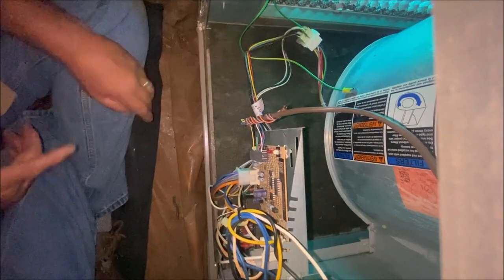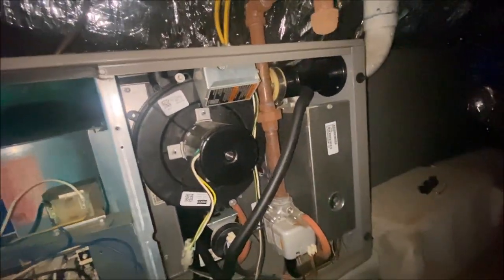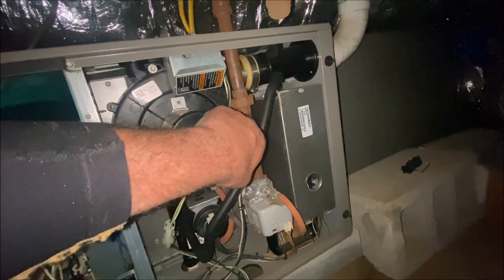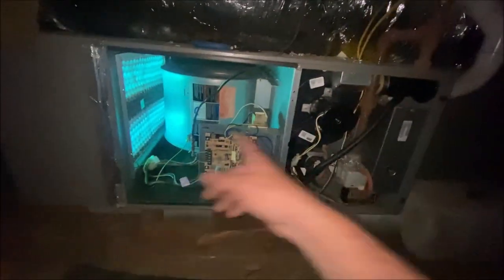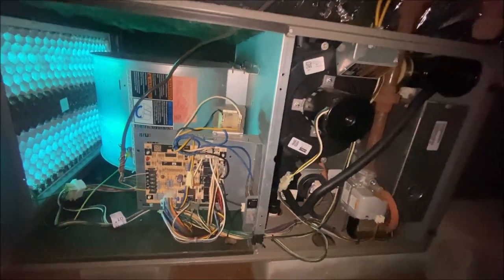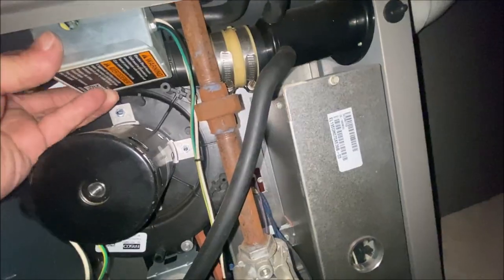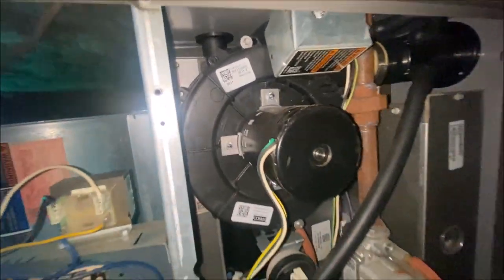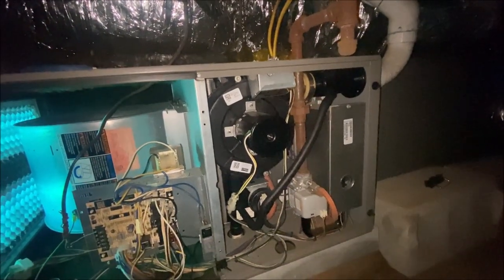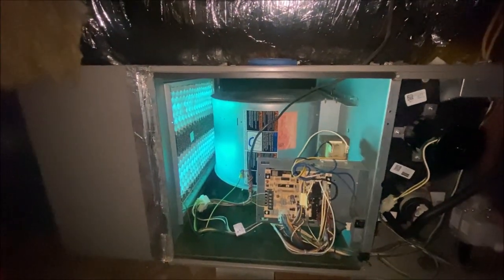As far as putting a board or a motor, transformer, switches — here's your resettable fuse. Now it doesn't look like it's going to be real easy — you're going to have to pull the gas line out to get this motor out. But you've got to give and take when you're trying to make a furnace compact like this one definitely is. So they did pretty good on this one — better than the old Pulse. The blower compartment — Lennox gets an A on that.